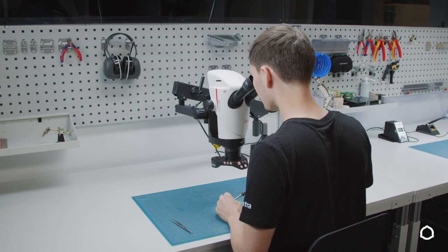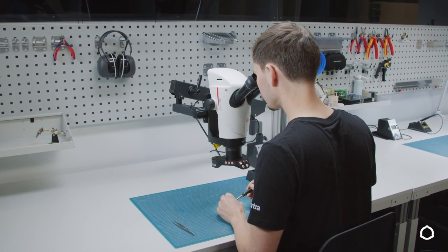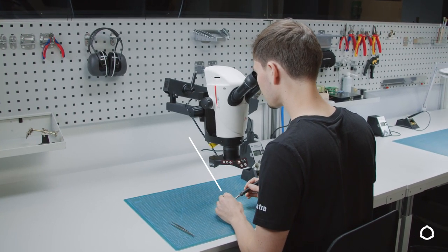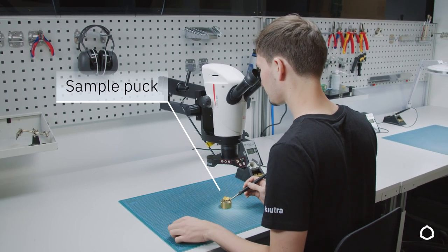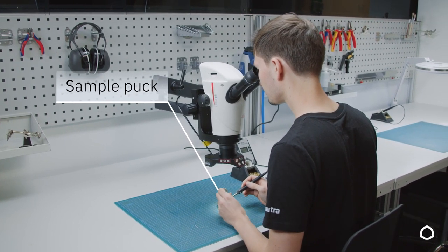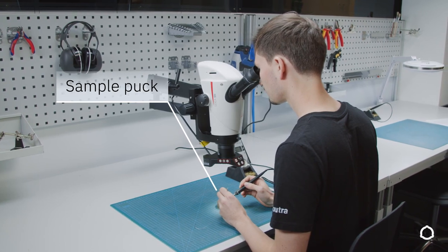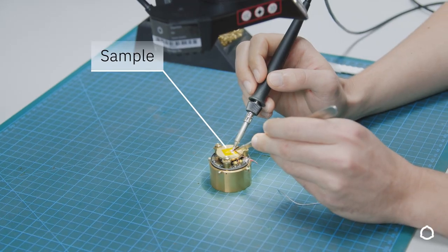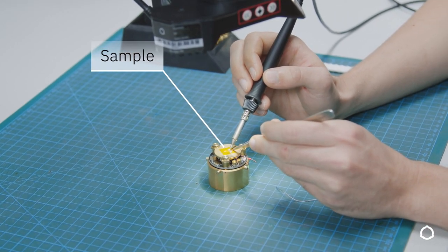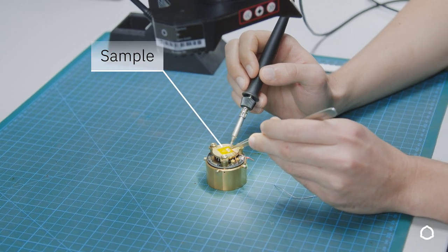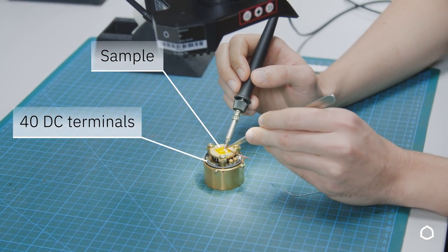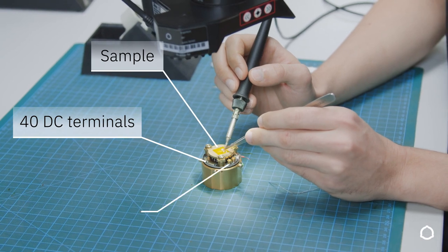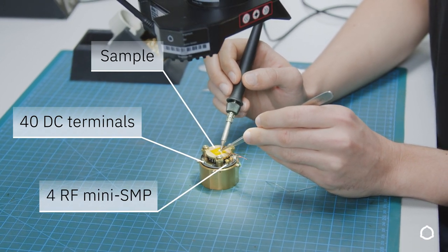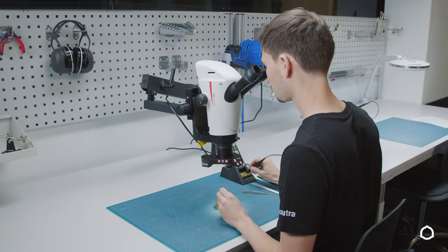The L-type rapid features our puck-based sample transfer mechanism, so the first thing to do is to prepare the sample on the sample puck. The sample puck has a platform which can accommodate customer setups and samples of up to 36 mm in diameter and 100 mm in height. The puck connects 40 DC lines via bondable terminals as well as up to 4 additional RF lines via mini SMP connectors.